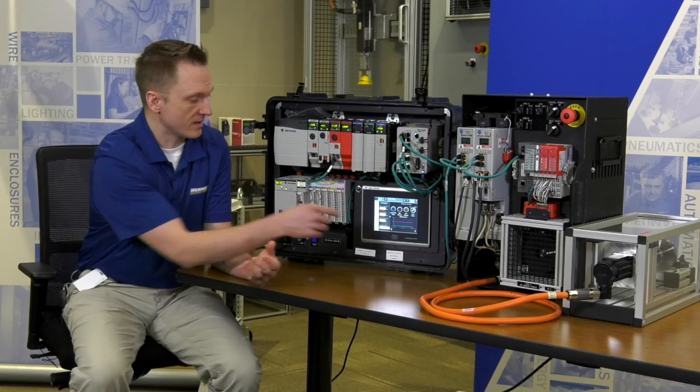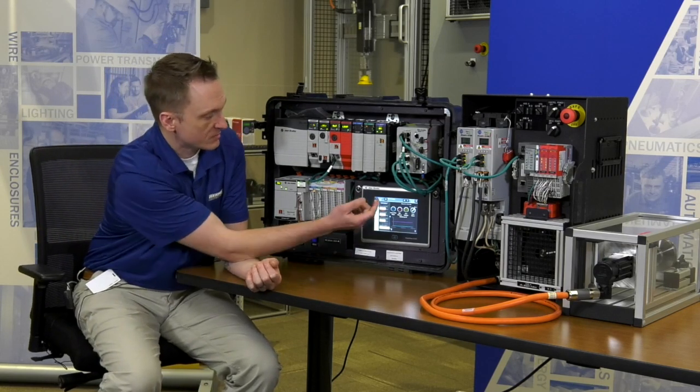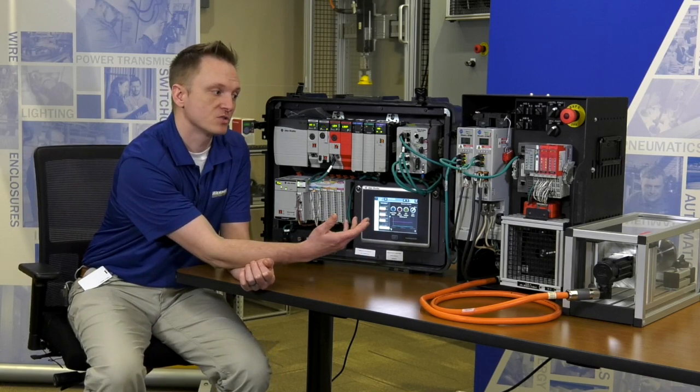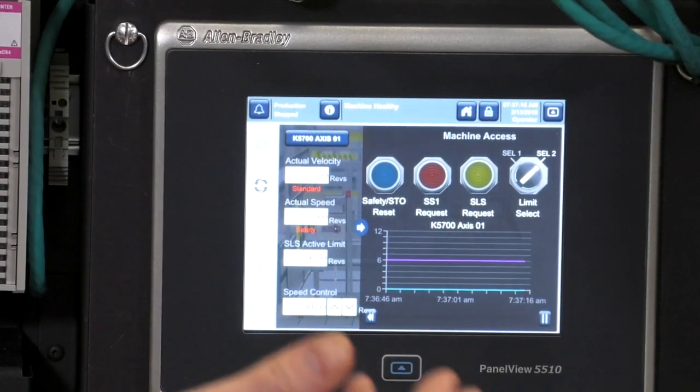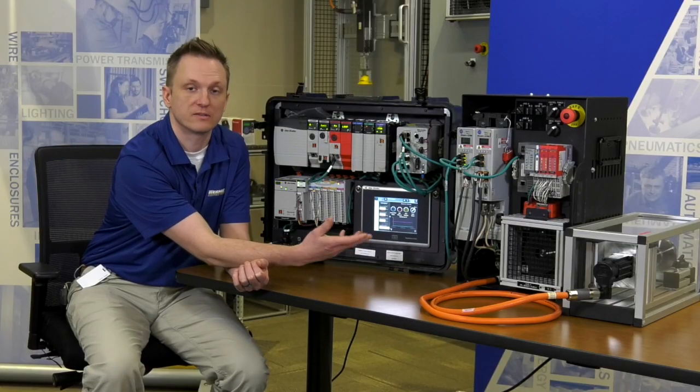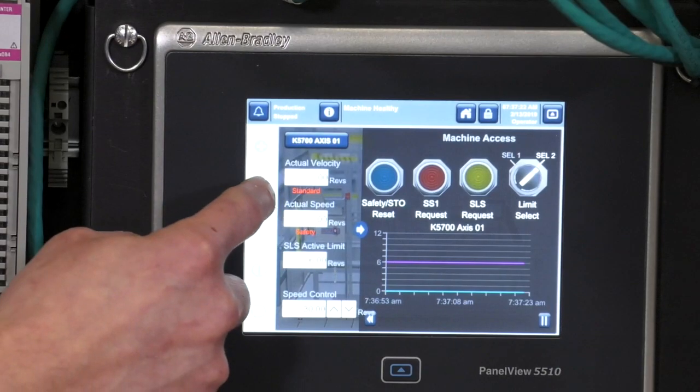So the first thing I'm going to do is on the PanelView 5510, I'm just going to get the drive ready to go and I'm going to initiate some motion. Once I get the motion ready, I'm going to initiate a Safe Stop 1 request, which is going to be a ramped deceleration to a stop, and then issue a Safe Torque Off. So I'm going to start the motor up.